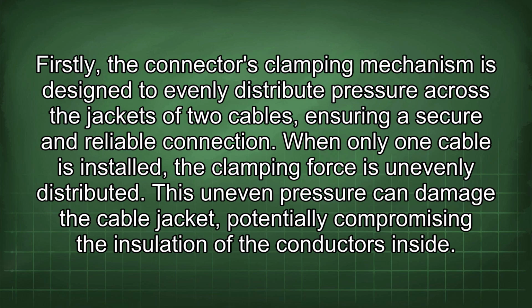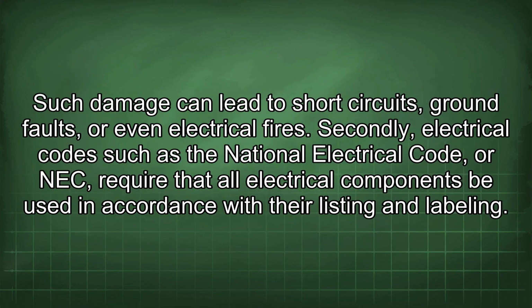Firstly, the connector's clamping mechanism is designed to evenly distribute pressure across the jackets of two cables, ensuring a secure and reliable connection. When only one cable is installed, the clamping force is unevenly distributed. This uneven pressure can damage the cable jacket, potentially compromising the insulation of the conductors inside. Such damage can lead to short circuits, ground faults, or even electrical fires.